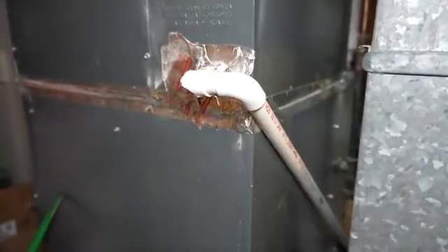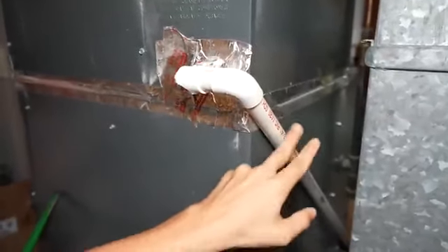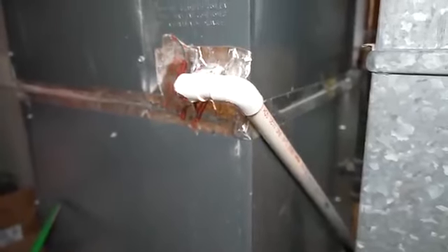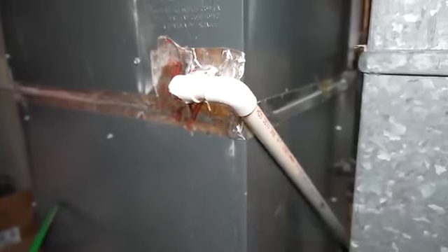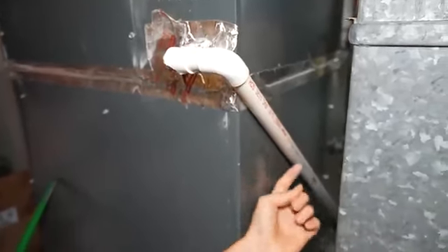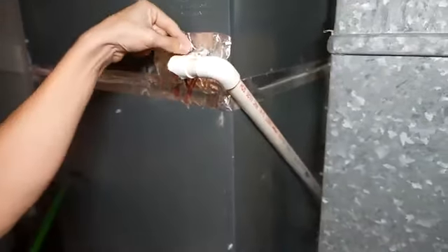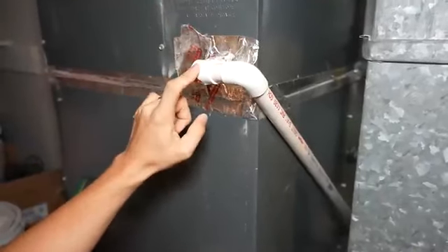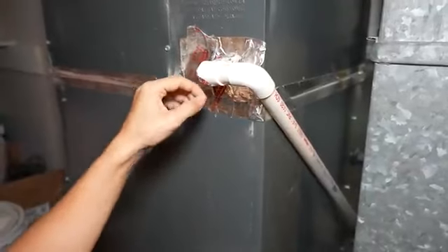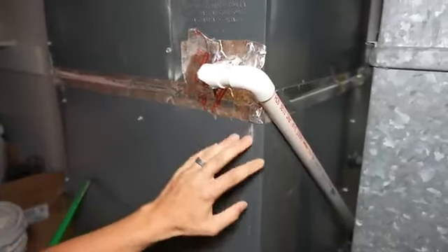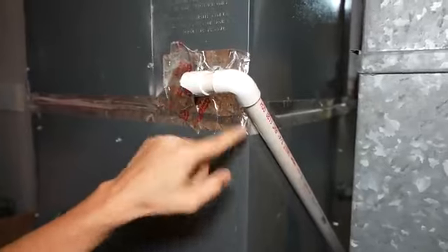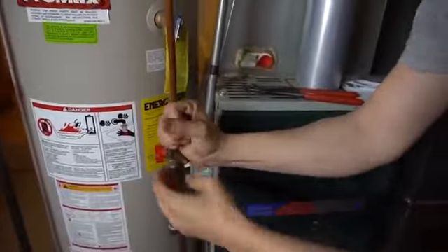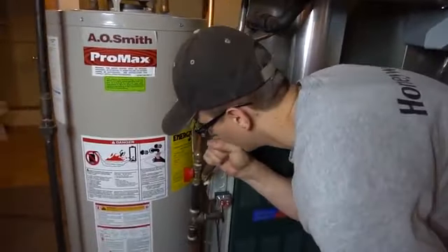So your options are either to cut it somewhere and then use a coupler to glue it back together. Or an even easier method is to simply get some compressed air and blow backwards inside of this pipe. Whatever is stuck is usually going to be right at this fitting right here. If there's anything stuck in here, you can blow it backwards and a bunch of water will come gushing out. So this system has a PVC condensate drain line. I also have a video where there was a clear hose and how I cleared that one out as well. If you want, you can check that video out.